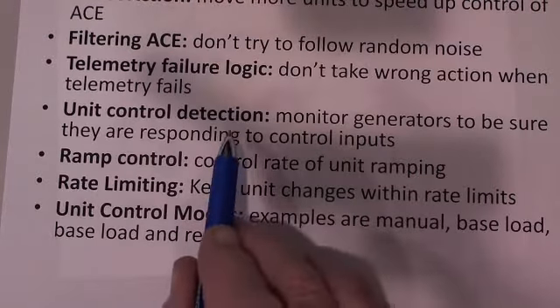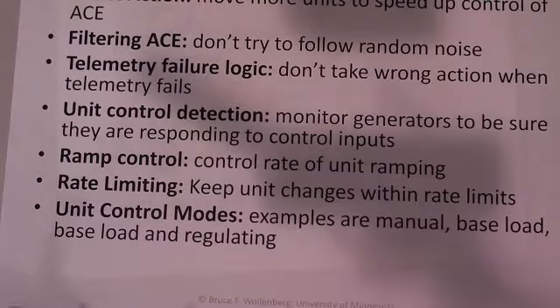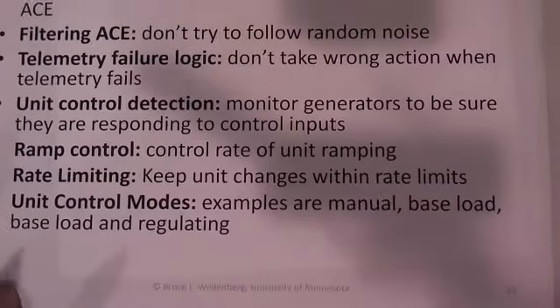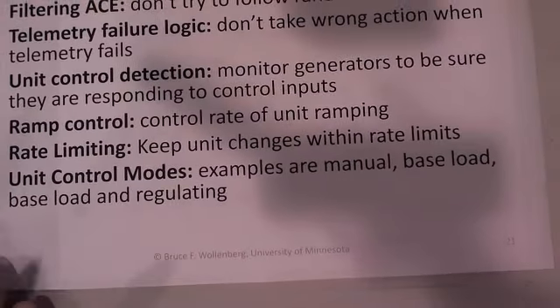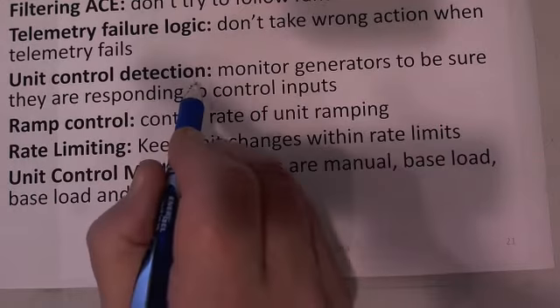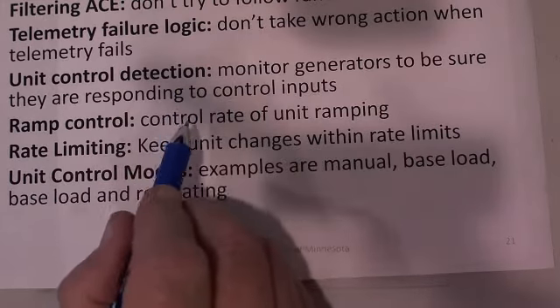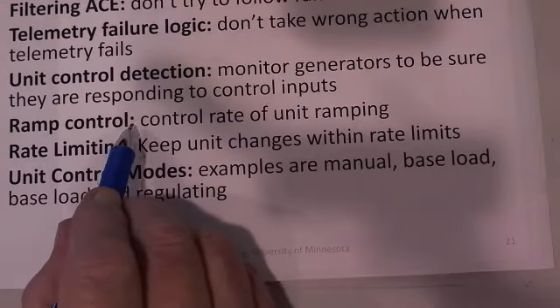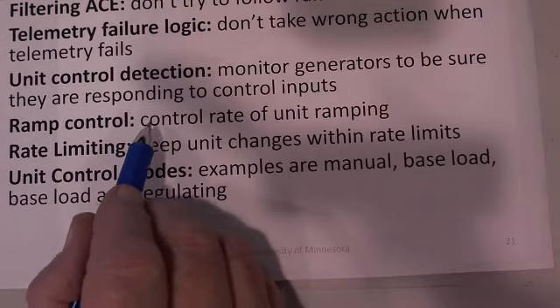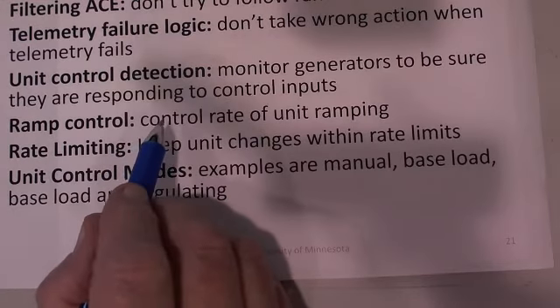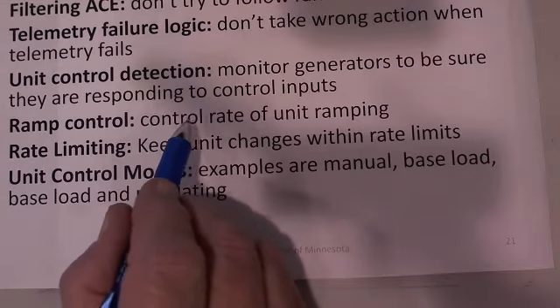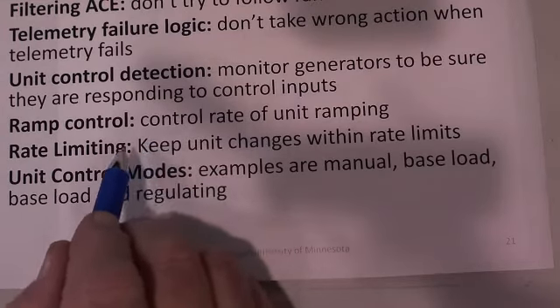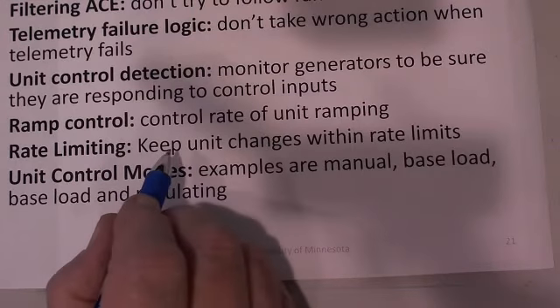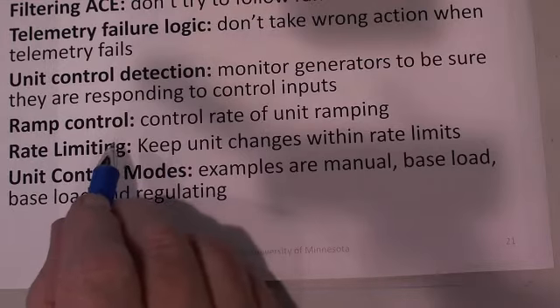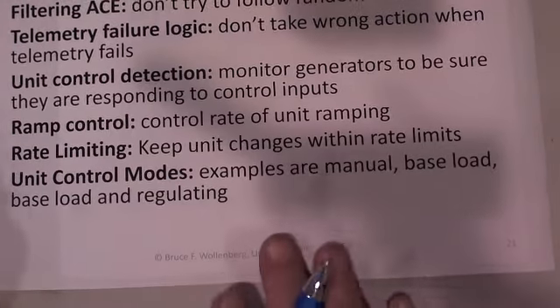Okay. Unit control. Is the generator not following the actions of the control system? That's very important. If it's not, you probably want to get an alarm out to the power plant. There's always people in a control room at a power plant. We'd like to be able to have ramp control where we set the generator and we say, I want the generator to increase by let's say 5% every hour or something like that, and I can ramp the output up at a certain rate. Rate limiting, I keep the unit from ramping up and down too fast, and so forth. There's lots of control aspects like that.